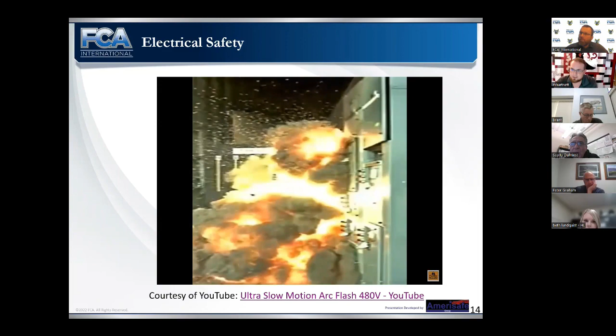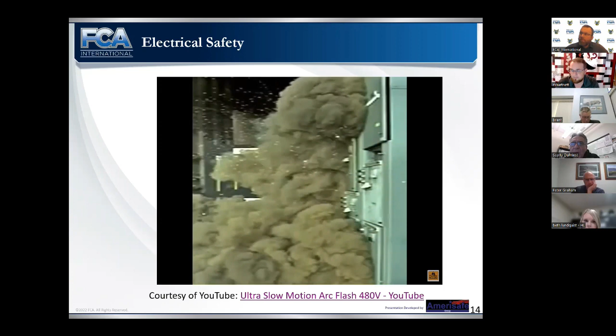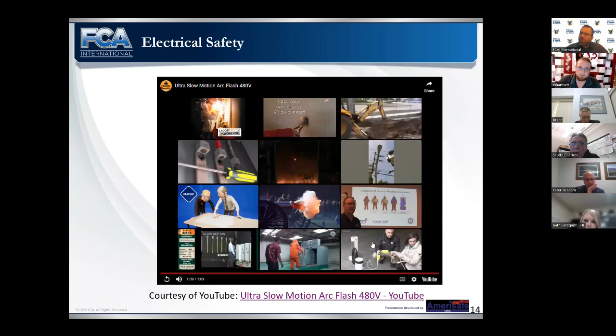And the arc flash gear that we give electrical workers to work in energized situations is not designed to protect employees from harm. It's designed to make the interaction survivable. Okay, the FR clothes that are provided to electricians will catch on fire at 3,600 degrees. Everything catches on fire at 3,600 or 36,000 degrees. They're designed to go out immediately within a certain number of milliseconds so that the secondary burns don't set in. And so you can see that kind of violence that we're talking about with that arc flash.